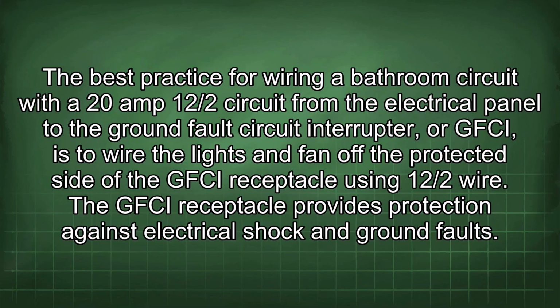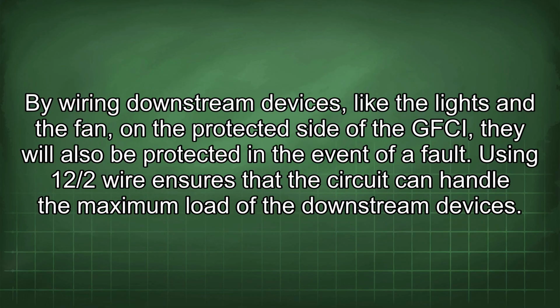The best practice for wiring a bathroom circuit with a 20 amp 12/2 circuit from the electrical panel to the ground fault circuit interrupter, or GFCI, is to wire the lights and fan off the protected side of the GFCI receptacle using 12/2 wire. The GFCI receptacle provides protection against electrical shock and ground faults. By wiring downstream devices, like the lights and the fan, on the protected side of the GFCI, they will also be protected in the event of a fault. Using 12/2 wire ensures that the circuit can handle the maximum load of the downstream devices.